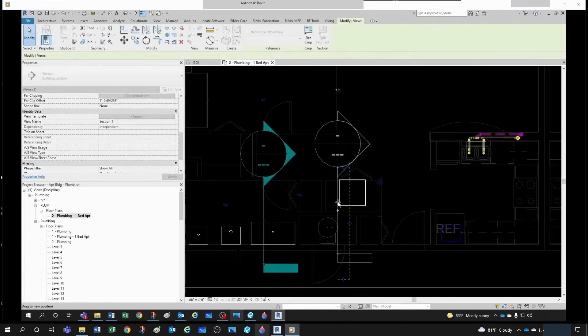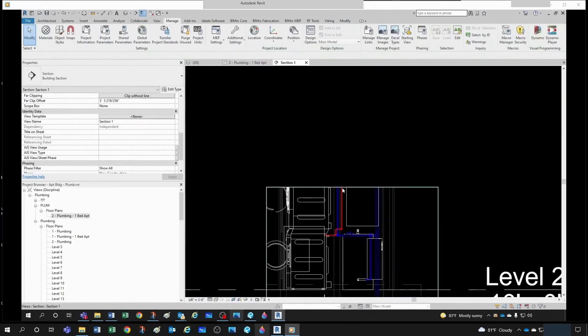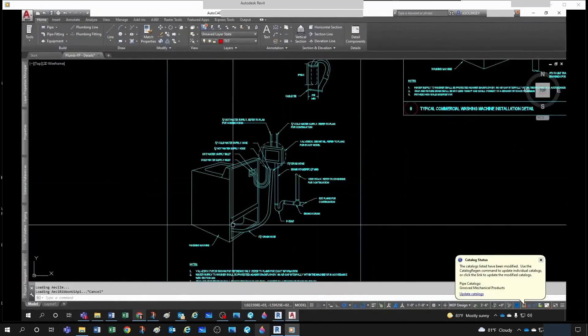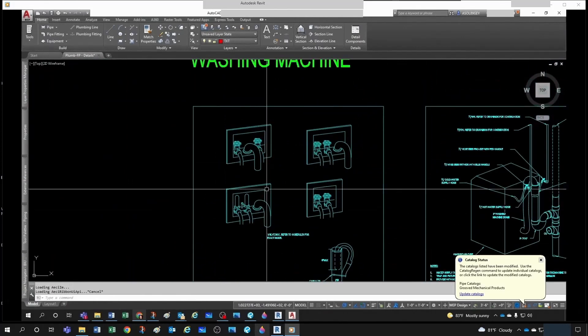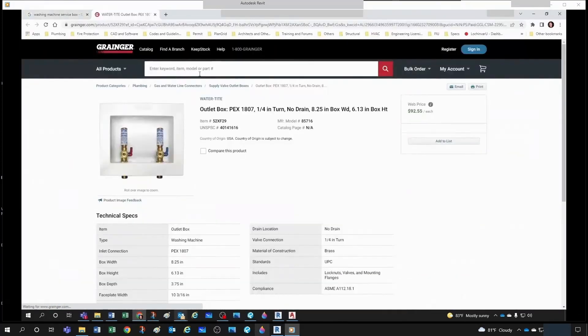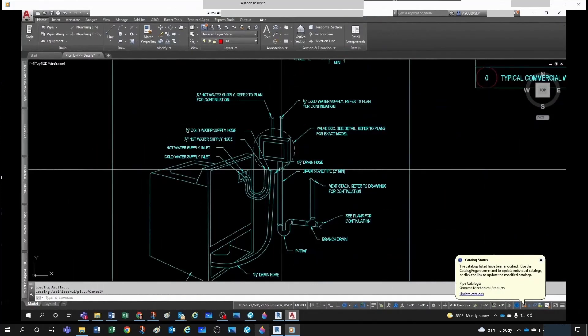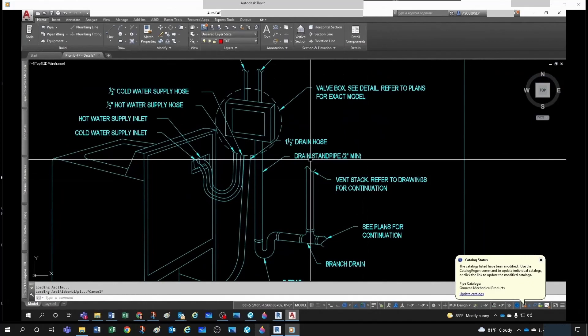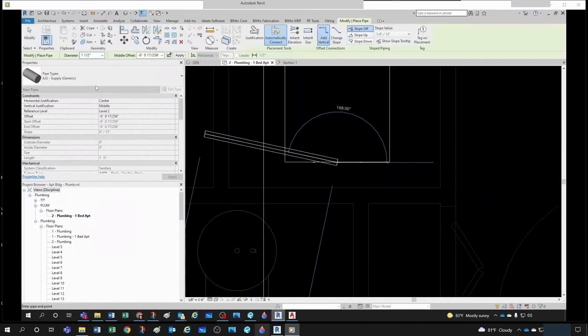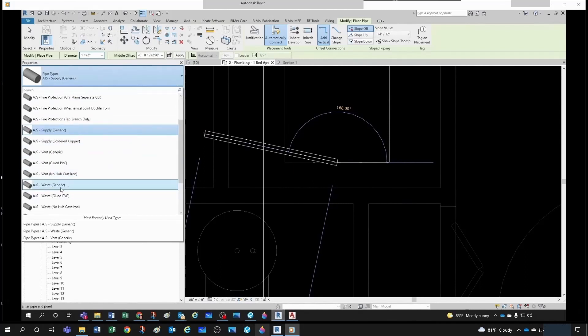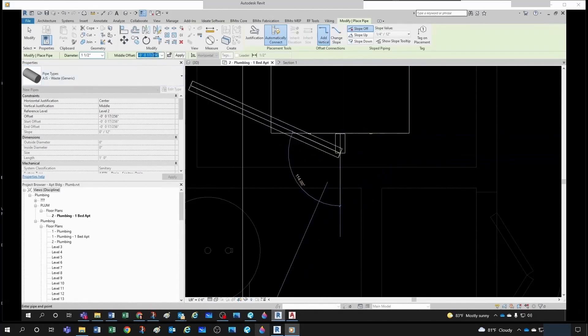Let's start with the washer and dryer — it's a combo unit — on Level 2. In reality, what you're going to have coming out of your washer is a one-and-a-half-inch drain hose discharging into a washer service box, which includes cold water, hot water, and sanitary drainage. Some of them come with hammer arresters already, which is nice. Downstream of that you'll have your tailpiece, your p-trap, and then your stack — your vent — and then you continue with drainage. For this example, we don't have a service box, so we're just going to tie in directly from the washer to keep the reading from the plumbing fixture.